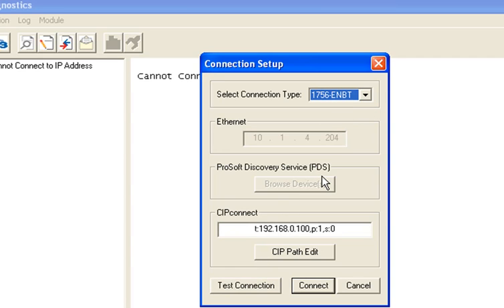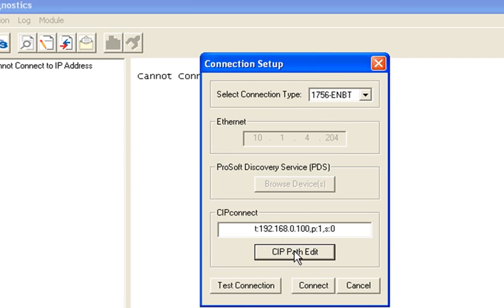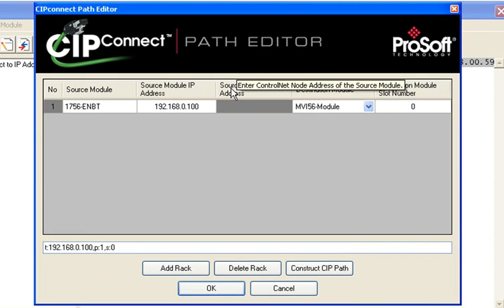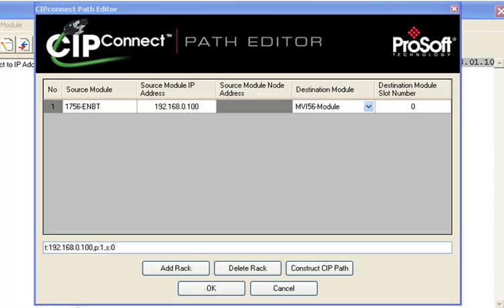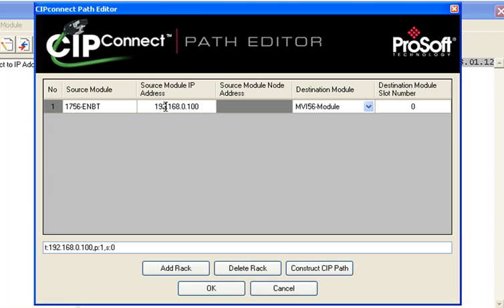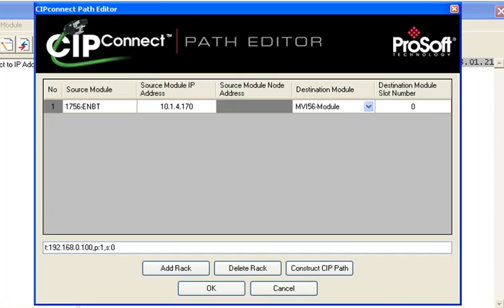Now what I'll do, I'll set it up the other way, going through a 1756 ENBT. So I'll click on CIP Path Edit and here's where you see the CIP Connect Path Editor window. Now I know that my source is going to be the 1756 ENBT and I happen to know my IP address of my ENBT. You can also use RSLinx to get that. Mine is 10.1.4.170.